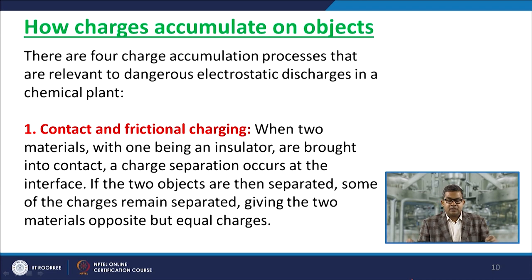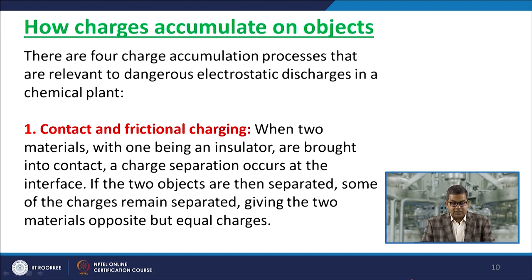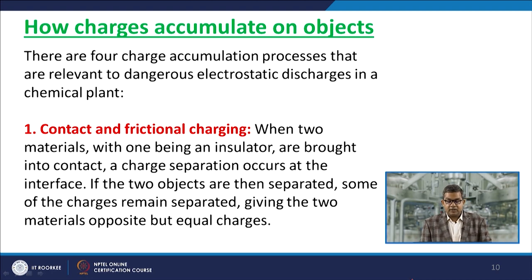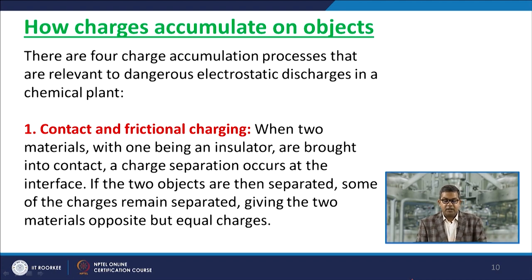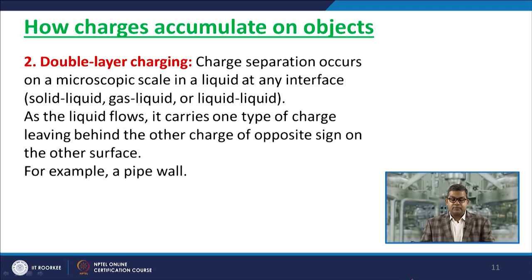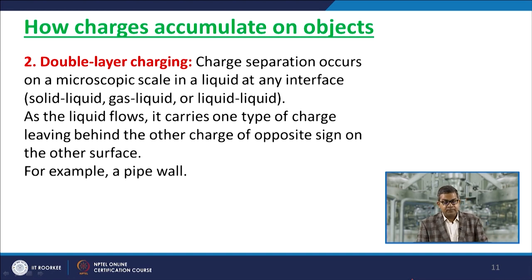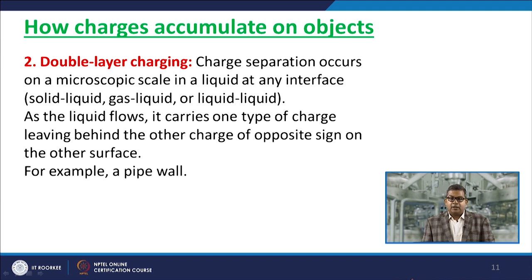There are four charge accumulation processes relevant to dangerous electrostatic discharge in a chemical plant. First, contact and frictional charging: when two materials, with at least one being an insulator, are brought into contact, charge separation occurs at the interface; upon separation, opposite but equal charges remain on each material. Second, double layer charging: charge separation occurs on a microscopic scale in a liquid at any interface — solid-liquid, gas-liquid, or liquid-liquid. As the liquid flows, it carries one type of charge, leaving the opposite charge on the other surface, such as a pipe wall.